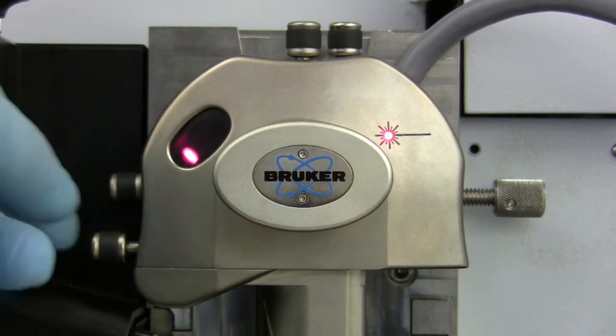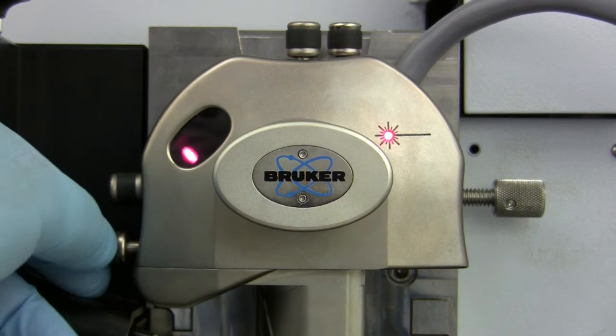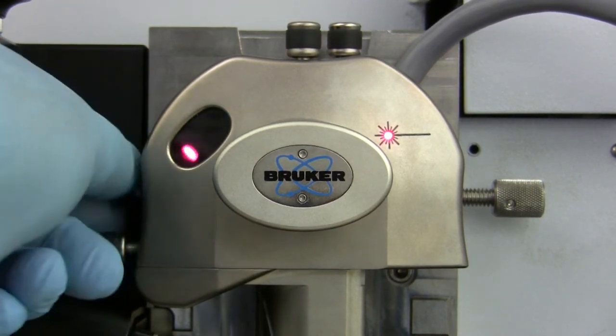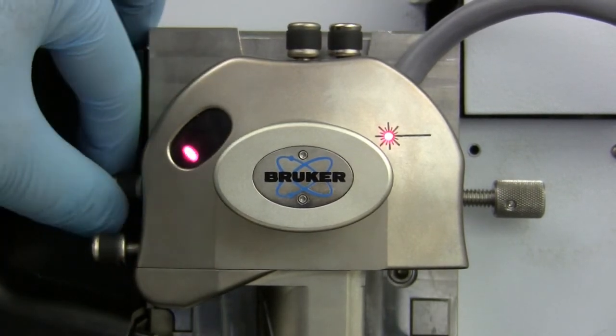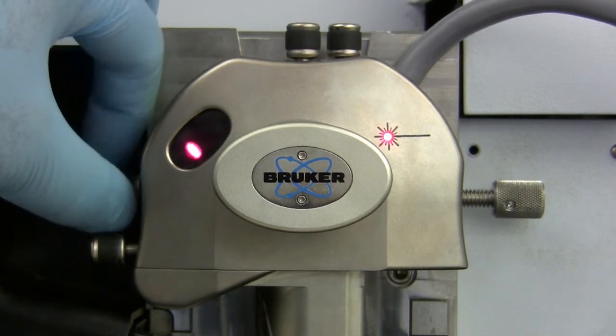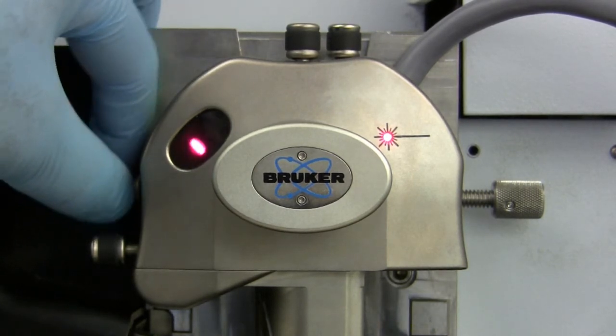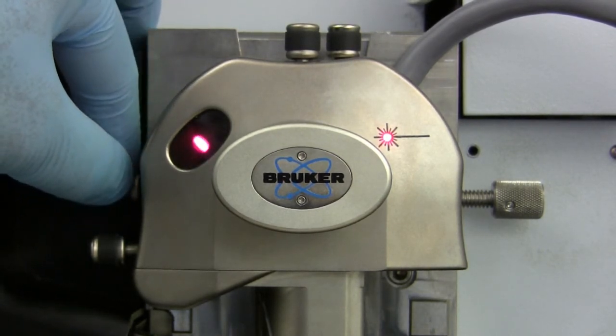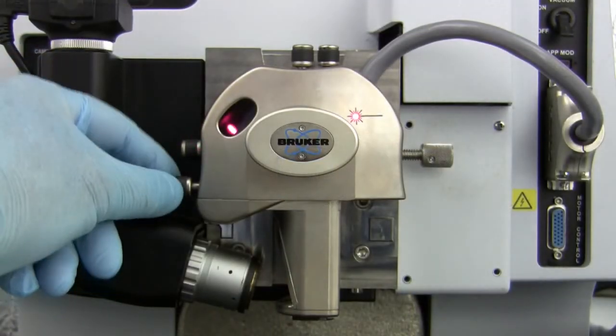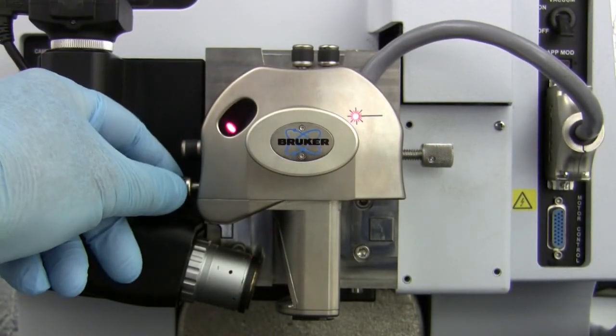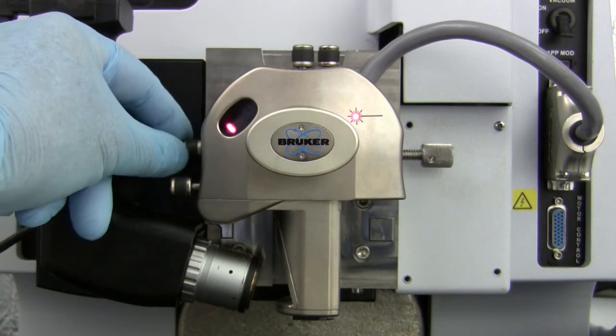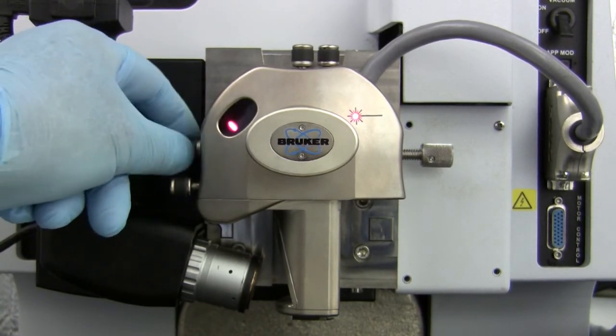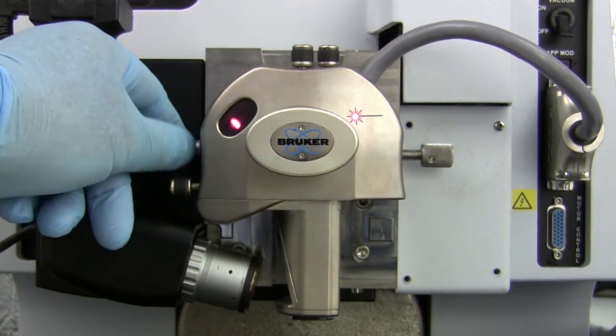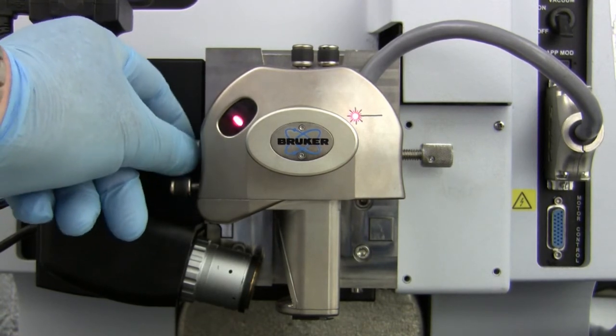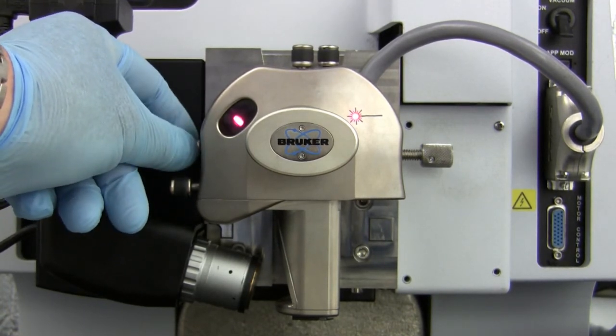Rotate the detector adjustment knobs to steer the reflected laser into the position-sensitive photodetector. The window on the left side of the head reveals the position of the reflected beam. Typically, the optimum position will be near the center of the window. Occasionally, the reflected beam may be too far off center to show up in the window. It may be necessary to rotate the detector adjustment knobs all the way into their respective stopping positions and then rotate them back out one at a time until the spot reappears.